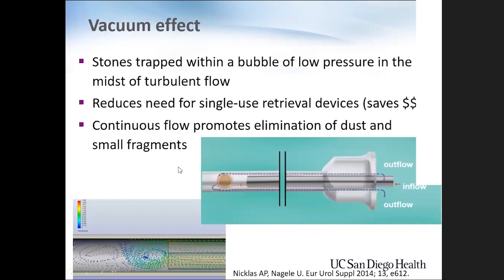So the vacuum effect, I think this is one of the main advantages of the MIP. It facilitates fast removal of stones, of both dust and also small particles. The idea is the inflow through the nephroscope, as shown by this red current, creates an eddy current approximately 1 to 2 centimeters in front of the tip of the camera. And then the draining fluid, which comes outside the sheath, because of the physics of that interaction, creates an eddy current right in front of the camera, which you can use to trap stones. And by withdrawing the nephroscope, you're actually withdrawing larger stone fragments in this eddy current. And then the continuous flow promotes smaller dust and fragments to also drain on their own at the same time. An advantage of this is it is potentially faster, and you don't need to use disposable retrieval devices such as baskets and graspers.